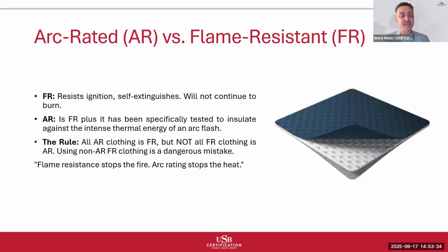Arc-rated materials are flame resistant, plus they have been specifically tested to provide thermal insulation against the instantaneous energy release of an arc flash event. The testing measures how much thermal energy passes through the material during a controlled arc exposure.